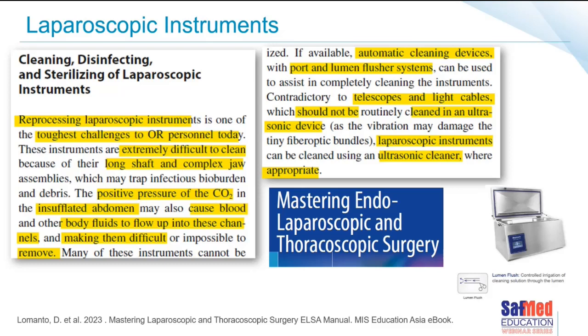So they go on to talk about the importance of using automated cleaning devices with port and lumen flushes. That, of course, can include your ultrasonic cleaner. If you're using an ultrasonic cleaner, it is going to help to use one that's got a lumen flush and not just irrigation on the outside, because you want to be able to flush and irrigate and put ultrasonics down the lumens, because these lumens are particularly difficult to clean.